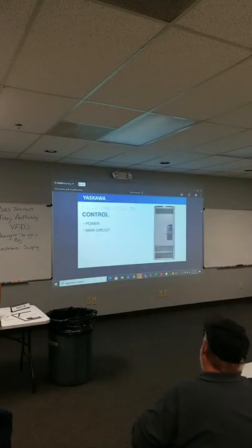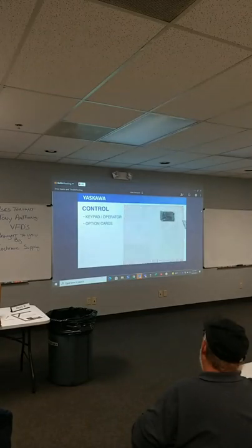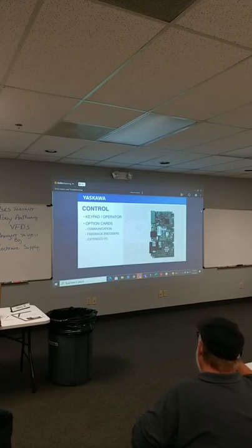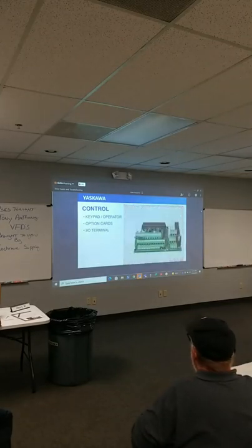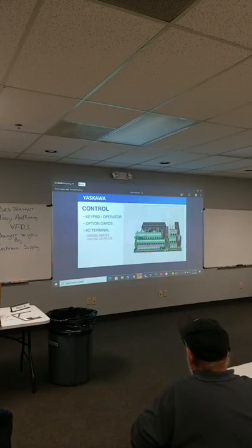We'll start with control. For most drives, the operator uses a digital keypad to program the unit for the given application, and in some cases, to operate the drive locally via the keypad. Things like overloads, accel and decel rates, minimum and maximum speed, and many other parameters can all be set through the keypad. For a user looking for some more advanced setups, there are option cards that can be added, which include communication options, feedback encoders, and extended inputs and outputs. For controlling purposes, the user can wire into the digital inputs and outputs and analog inputs and outputs. The I/O terminals also support some communication protocols.